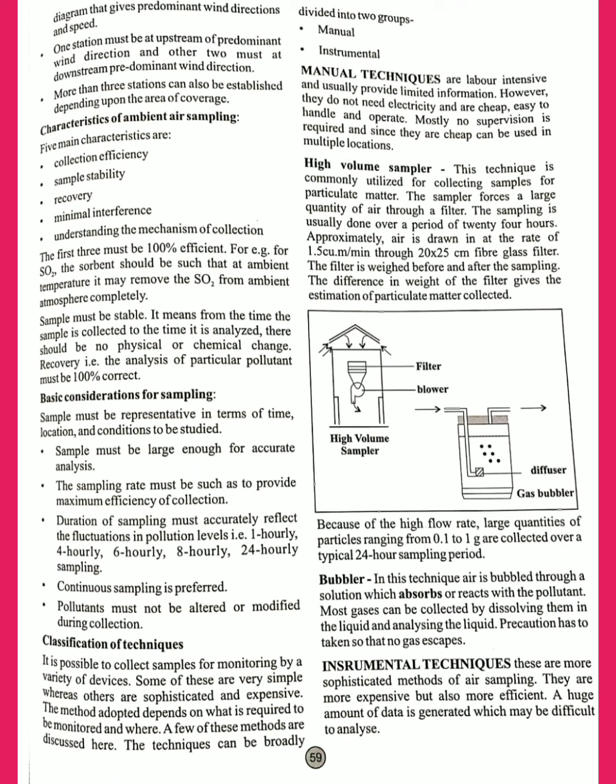The high volume sampler technique is commonly used for collecting samples for particulate matter. Here, the sampler forces a large quantity of air through a filter. The filter is weighed before and after sampling. The difference in weight gives the estimation of particulate matter collected. Because of the high flow rate, large quantities of particles ranging from 0.1 to 1 gram are collected over a typical 24-hour sampling period.